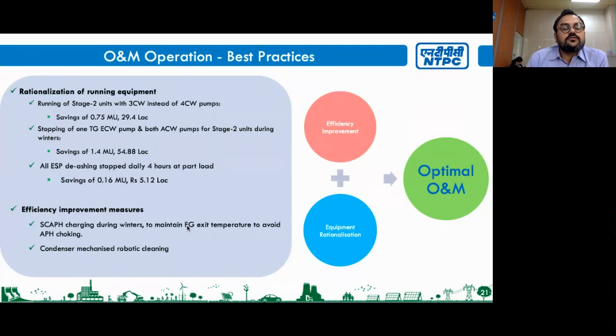We also have a practice of stopping 1 TG ECW pump and both ACW pumps for stage 2 units during winters when the temperatures allow us. Also, our stage 1 ESP de-ashing system is stopped 4 hours daily to facilitate some APC saving, because units are running on part load and not enough ash is getting generated for us to run the ESP de-ashing system constantly.